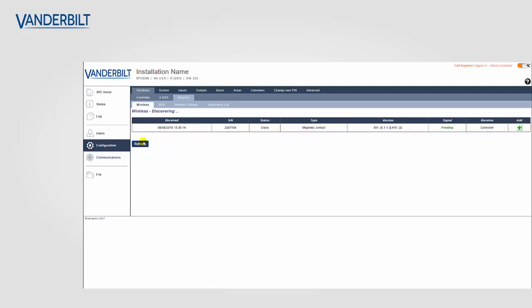We can now check the wireless discovering page. In this case I've refreshed the page to speed up the process and we can see that the device has learned onto the system. At the moment this device status is pending, meaning it has been discovered, but we have not initialized it onto the system as a zone number.